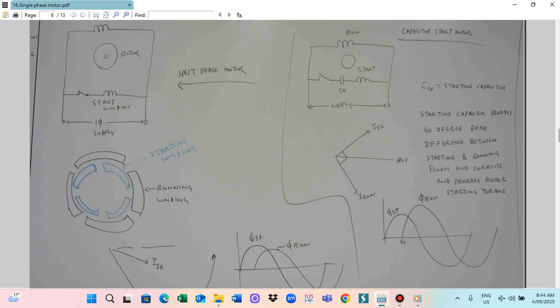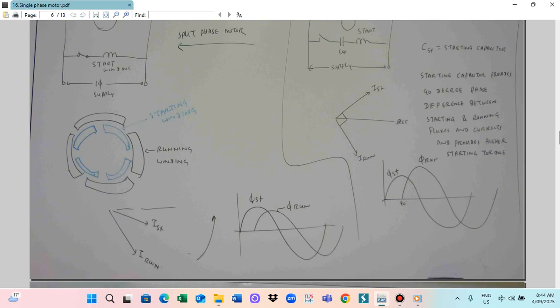For example, we can use this for the running winding. When you see the motor, the first thing we use, this black one, is the running winding. The running winding is the first thing we put at the back, and then on top of the running winding, with a 90 degree phase difference, we put the starting winding. So this blue one is the starting winding. The running winding is the black one and the starting winding is the blue one, so that the windings are 90 degrees out of phase. So in the middle, we have put the starting and the running winding.